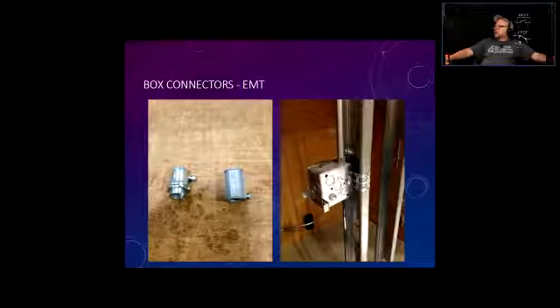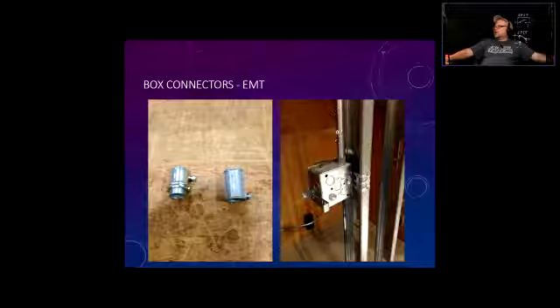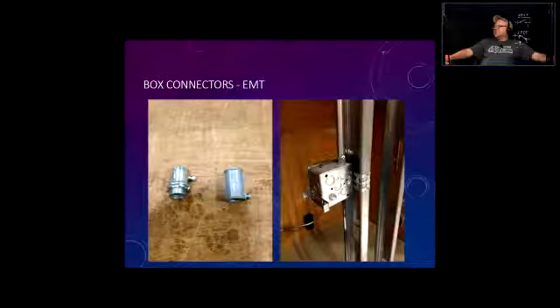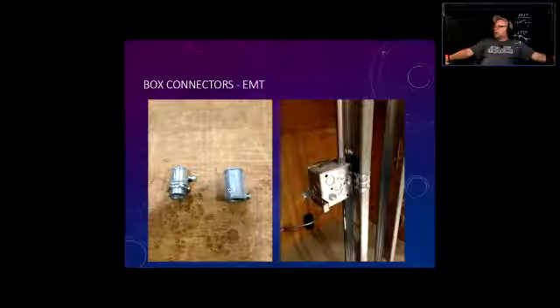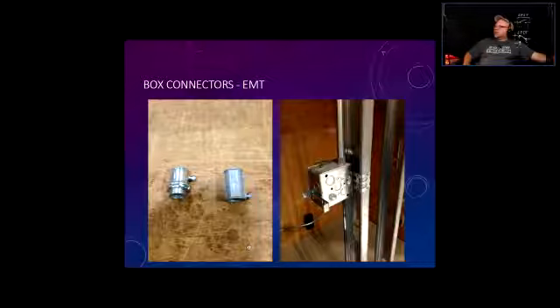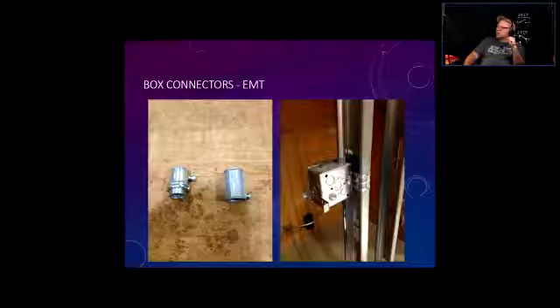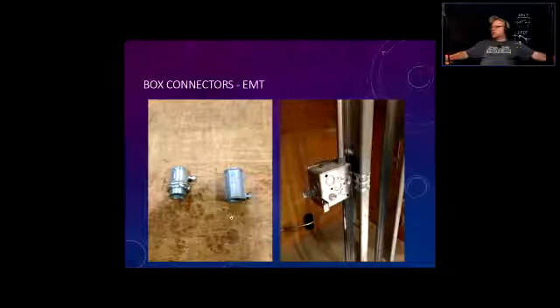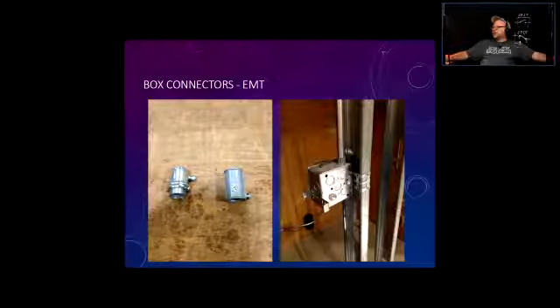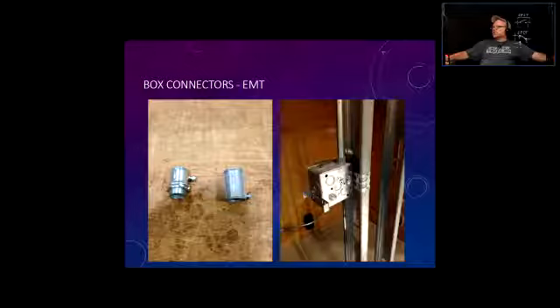Here's a connector that accommodates EMT – Electrical Metallic Tubing. This part goes onto the box knockout and a set screw fastens the metallic tubing. This other piece is a coupler – if you need to run over a longer distance, EMT comes in 10-foot sections, so for 50 feet you'd use about five sections. The coupler joins two pieces together. And here's a bracket to mount the square box to steel studs.